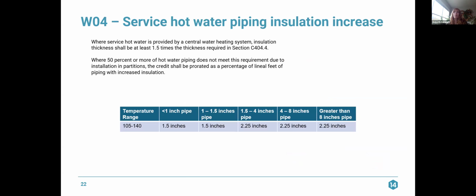W04 is service hot water piping insulation increase. Where your service hot water is being provided by a central system, the insulation thickness shall be at least 1.5 times the thickness required in section C404.4. So what I did was I took that table from section C404.4 and I just took this one temperature range because I wanted to just use it as an example. So we're looking at a temperature range of 105 to 140. Based on your pipe size, this is the amount of insulation that's going to be required to achieve credits under W04. If 50% or more of your hot water piping does not meet this requirement because you're installing it in partitions, then the credit shall be prorated as a percentage of lineal feet of piping with increased insulation.